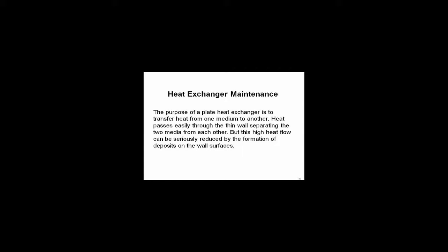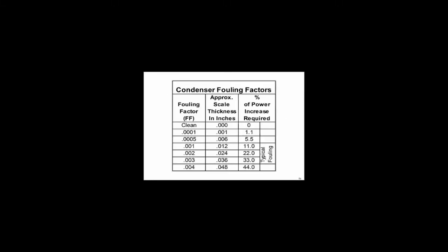Now, as designers, we want to save the energy. We want to do the right thing here, and the right thing is to get them cleaned up, and that way we don't turn them off. So what are we getting at? Here's what happens when you foul a heat exchanger. This is pretty typical, whether it's a chiller, evaporator, or a plate, or a single pass setup, it doesn't matter. As you foul a heat exchanger, your efficiencies go way down. Your power required go way up. In other words, your efficiency in a heat exchanger just deteriorates rapidly. We obviously want to keep them clean because keeping them clean, we've got that efficiency in place. This is a pretty picture, huh? Typical plate that we see sometimes with no maintenance being done and no system to keep them clean.